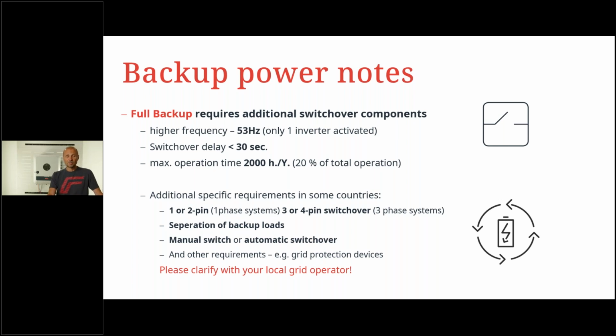Then we need to separate the backup loads. That's also sometimes required because of the high power needed. If you have more than, let's say, 10 kilowatt required, it can of course be difficult to start up the inverter. Therefore, it's very often good to split up the loads into specific backup power loads and standard loads, which are not so important. They can also be switched off when there's a grid outage.